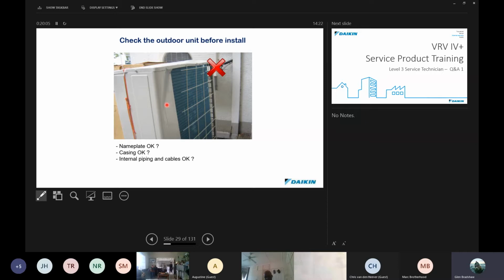Okay, and also when installing units, we want to make sure that when they're placed from the transport on site onto the installation location, that they're not damaged in any way. Okay, and then also just check the internal piping and cables and make sure that nothing's come adrift and that everything is in the right place, no cables are snapped or piping is cracked.